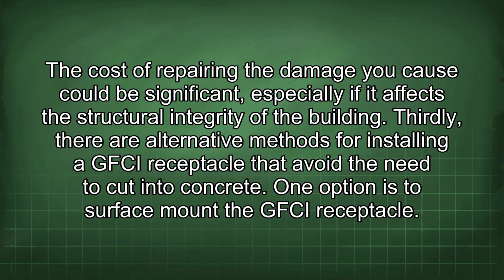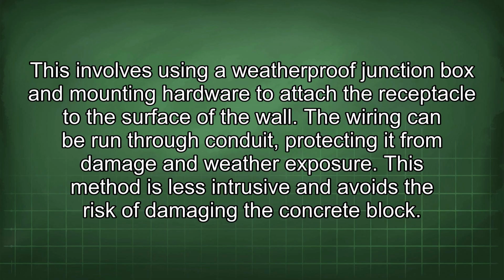One option is to surface mount the GFCI receptacle. This involves using a weatherproof junction box and mounting hardware to attach the receptacle to the surface of the wall. The wiring can be run through conduit, protecting it from damage and weather exposure. This method is less intrusive and avoids the risk of damaging the concrete block.